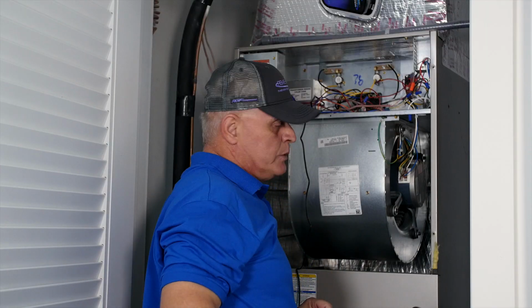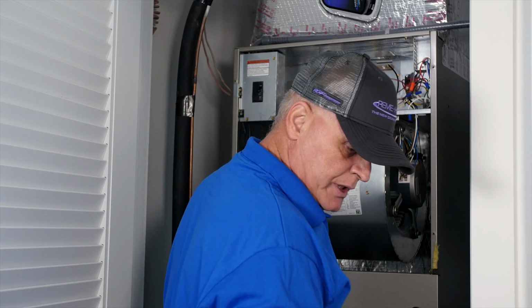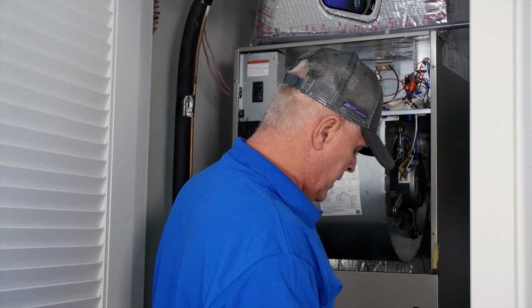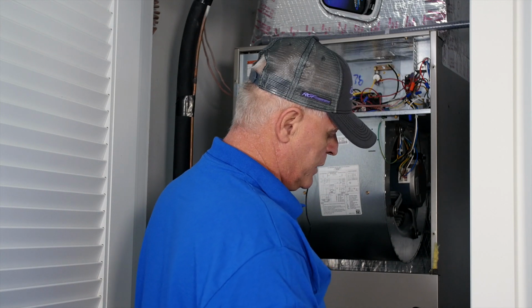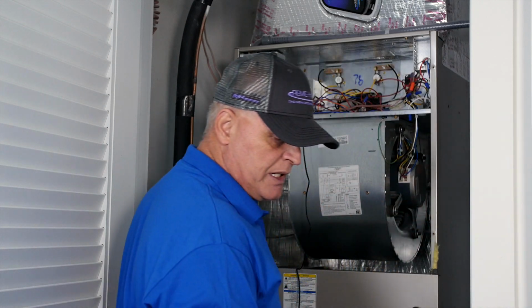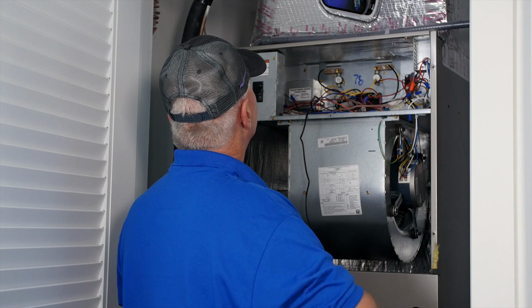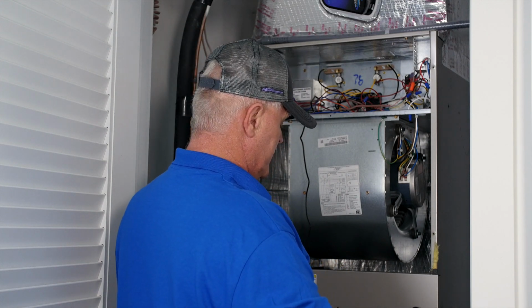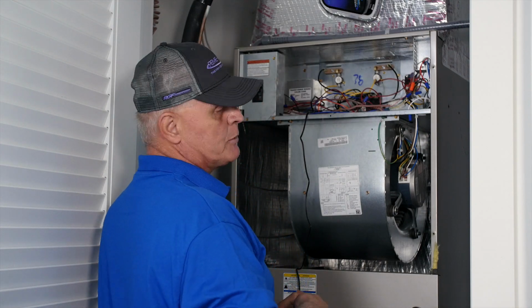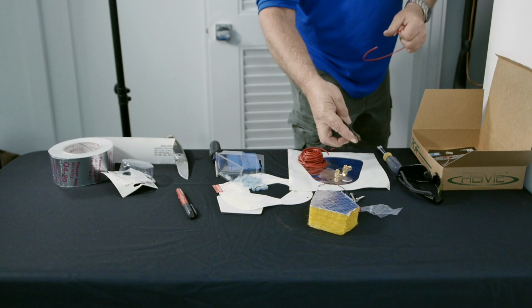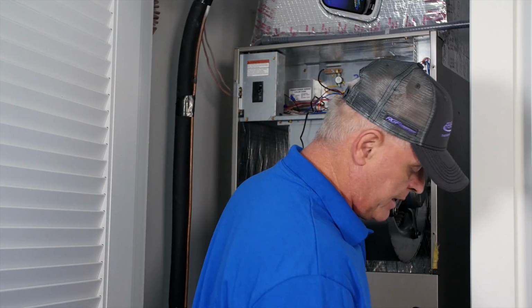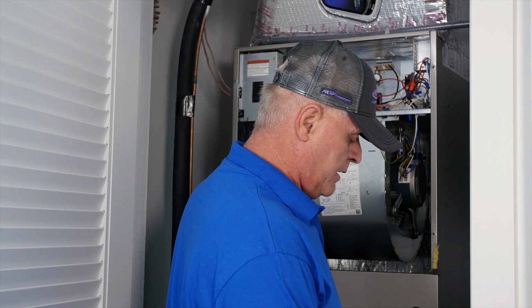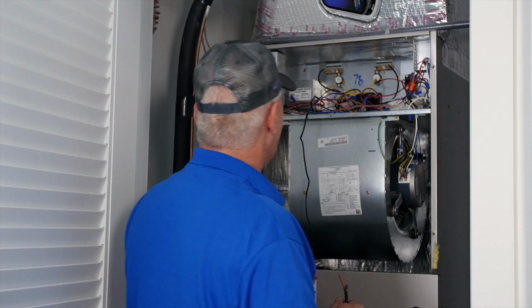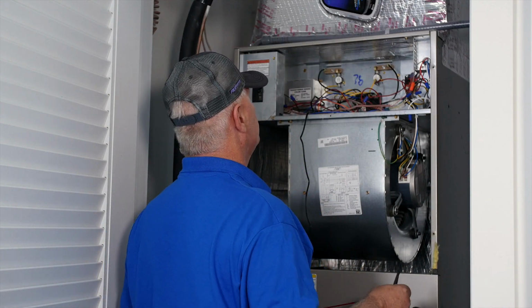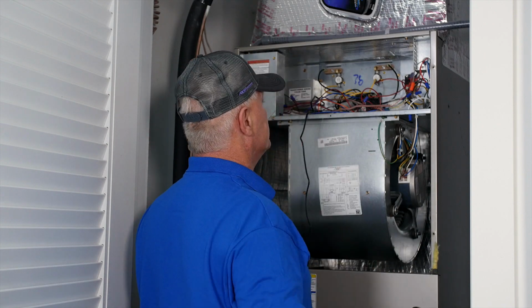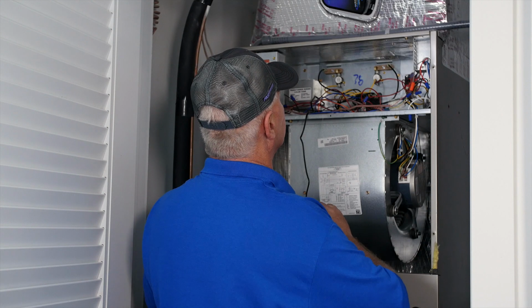If this was a gas unit with gas heat using a 2-speed motor, instead of connecting it to the heat relay as I have done, you would be connecting it to the low speed tap on that 2-speed motor, as that is what gets energized in heat and gives us our signal. So you would be connecting terminal 5 to the low speed relay of the fan motor on a 2-speed fan with gas heat. If you're using a gas heat unit which does not have a 2-speed motor, which has a variable speed motor, then you're going to be using our alternative air switch kit, which we will be showing you in a different video.